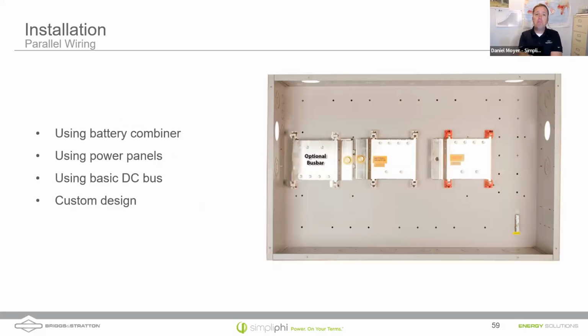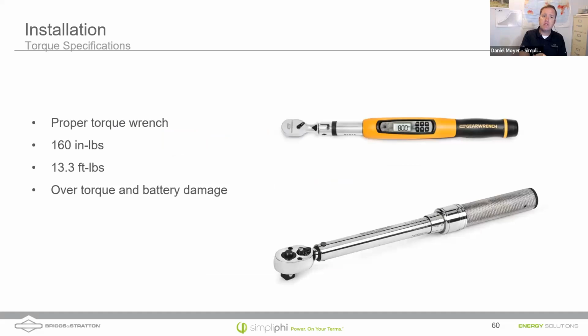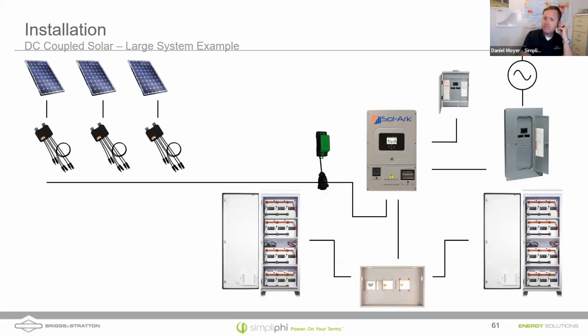An example here would be this Midnight Solar combiner. But there's bus bars, and there's also terminal blocks that I've seen used. Always please get out your torque wrench. I'd like to see 160 inch-pounds on the battery terminals. Don't use an impact driver. Ideally, you'd want to see an insulated torque wrench, like the one at the top. The one at the bottom is uninsulated and non-digital. Here's a couple examples of what it can look like.